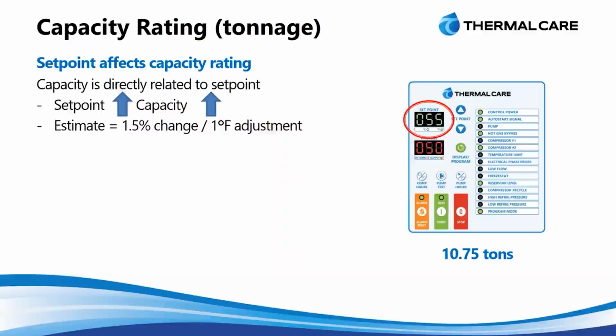In the other direction, if we have to lower that below 50, so we need a colder temperature, we'll actually reduce the nominal rating. So we'll go under that 10 tons. And all of that is dependent on what the process requires. Our units have a range from 20 degrees Fahrenheit up to 80 degrees. So there's a wide variety of different scenarios that require different temperatures. So we want to be aware of the effect that it has on a chiller's capacity.